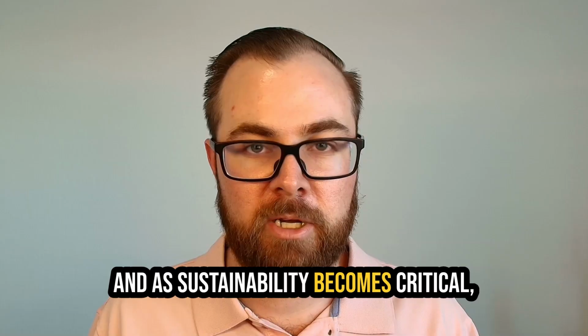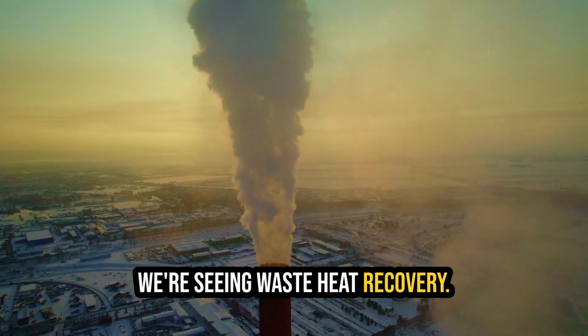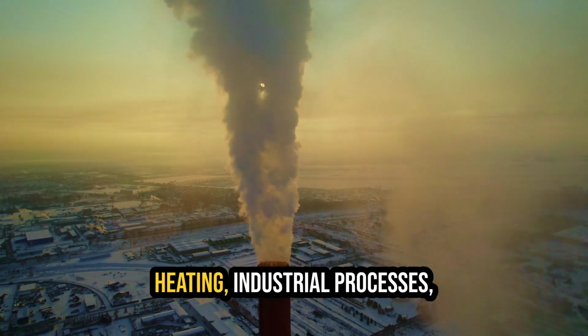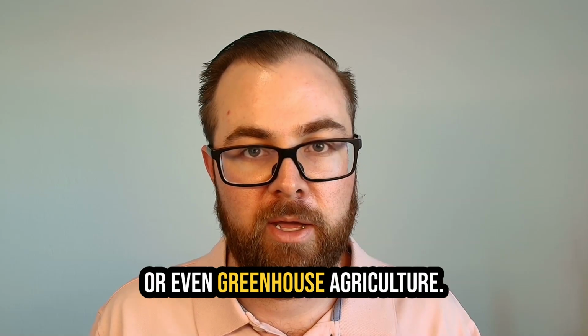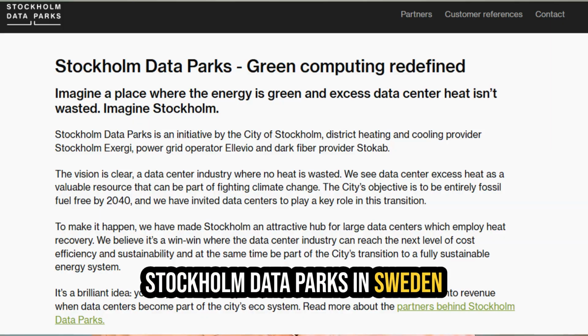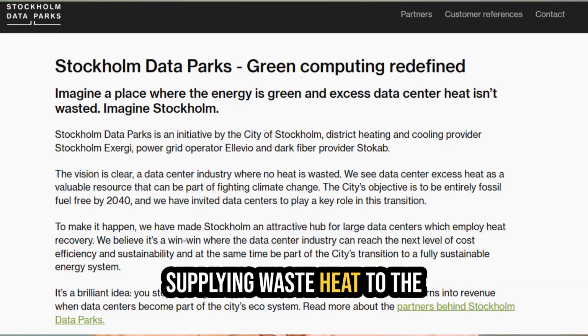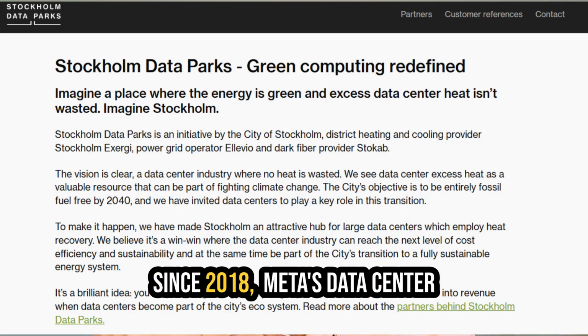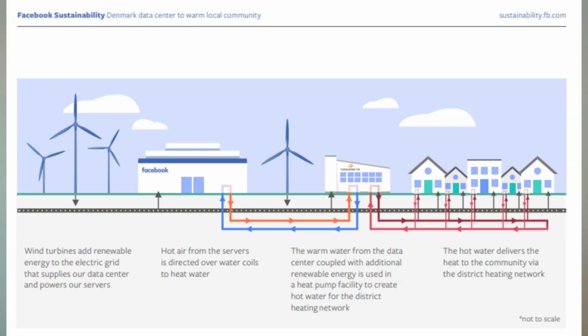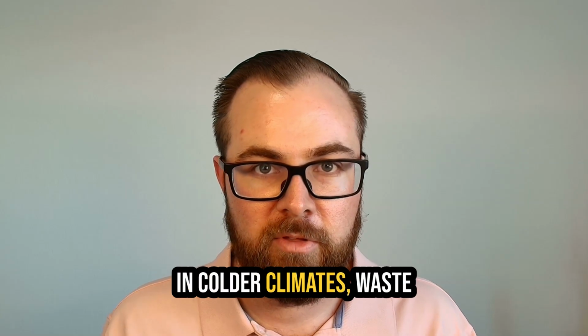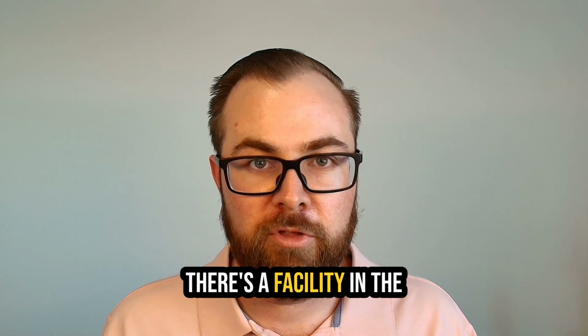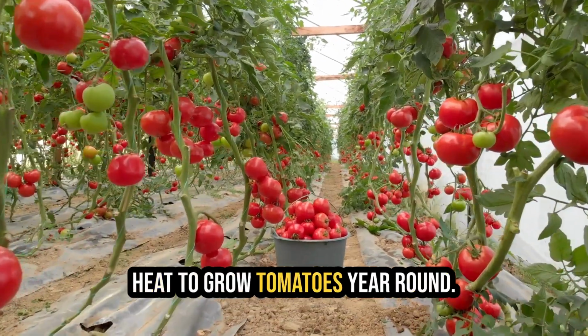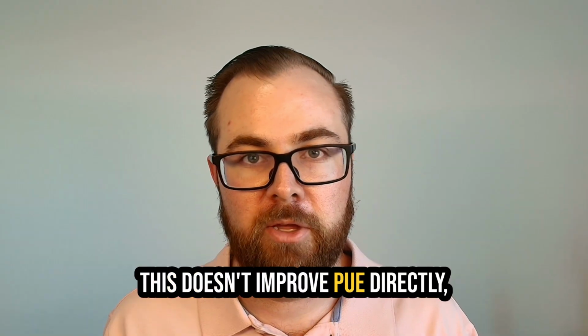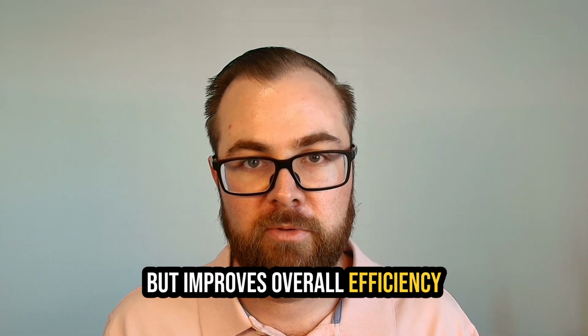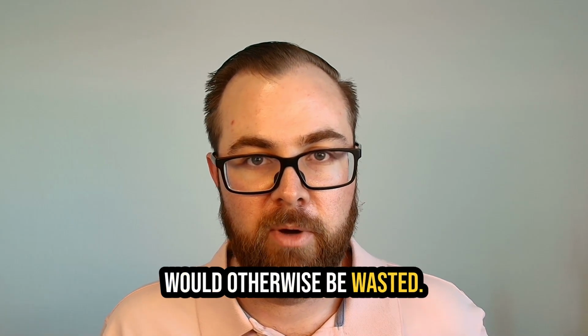And as sustainability becomes critical, we're seeing waste heat recovery. Using data center heat for district heating, industrial processes, or even greenhouse agriculture. Stockholm Data Parks in Sweden has become a pioneer here, supplying waste heat to the city's district heating network since 2018. Meta's data center in Odense, Denmark, provides heat to 100,000 residents. In colder climates, waste heat warms greenhouses. There's a facility in the Netherlands using data center heat to grow tomatoes year-round. This doesn't improve PUE directly, but improves overall efficiency by making use of heat that would otherwise be wasted.